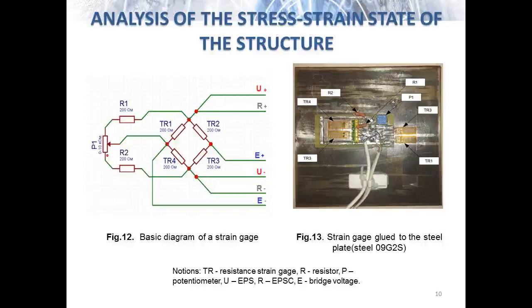All the sensors were tested on a calibration beam and in a climatic chamber in order to check temperature compensation using the plate made of steel. The sensors were glued to the previously prepared surface of the tank wall using a cyanoacrylate adhesive. Surface preparation involves grinding of the part of the tank wall to a smooth surface, which should be free from corrosion products and ensure the best adhesion. The strain gauges were connected via the 6-wire circuit to the input signal units of the firm OWEN. The measurement error of this device is 0.05%. The modules were combined via the two common RS-485 buses and connected to the PC. In order to minimize the distortion of the sensor signal, the input signal units were located in close proximity to the strain control points and connected with shielded cables. The measuring equipment was also protected against moisture and dust.